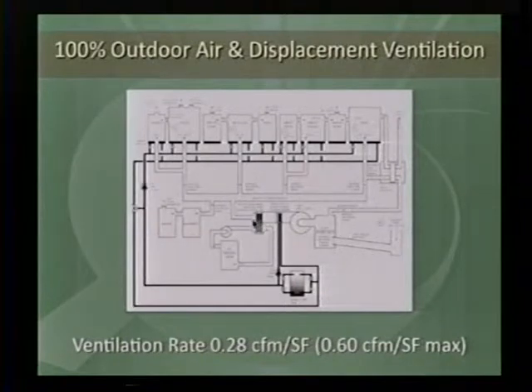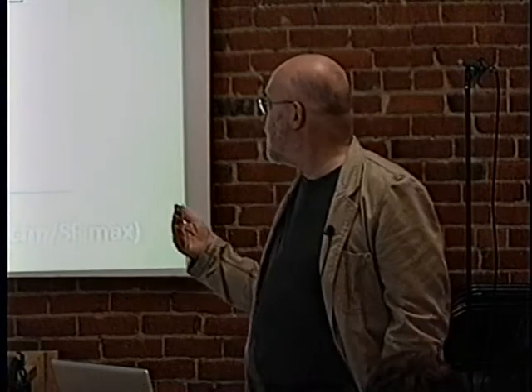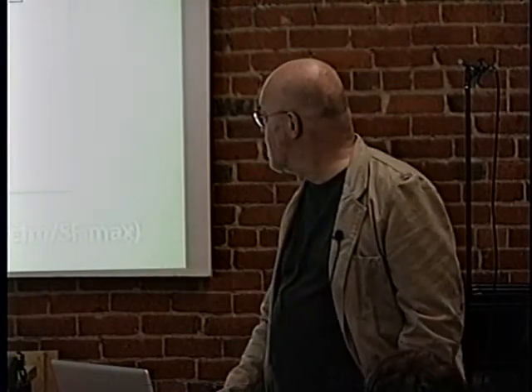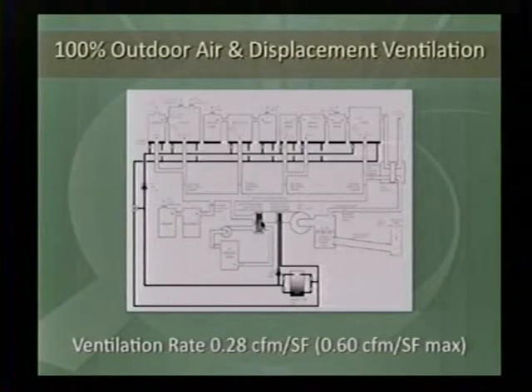And we put that in, and the heat pipe didn't work as well as we thought it would. Well, part of the problem was in the 3 years between the two projects, the project before this one and this project, inverter technology had gotten better, their efficiencies were better, and their waste heat had dropped. So we didn't have as much waste heat as we thought we would. And it seemed to dissipate pretty well into the basement walls anyway, so there wasn't a lot of availability. But the other thing was this heat pipe seemed to be working in reverse. It was taking energy in the wrong direction, and so we pulled the heat pipe out and put a reheat coil in that came off of the service hot water system.